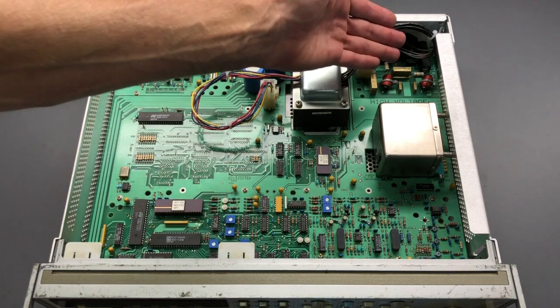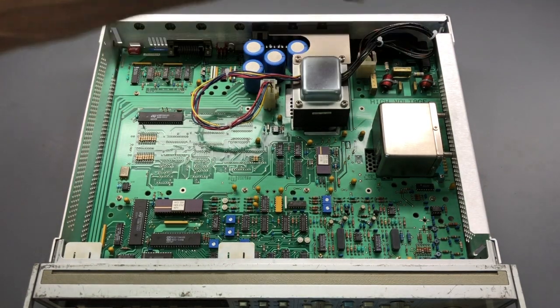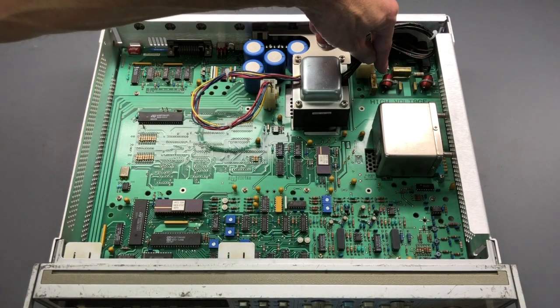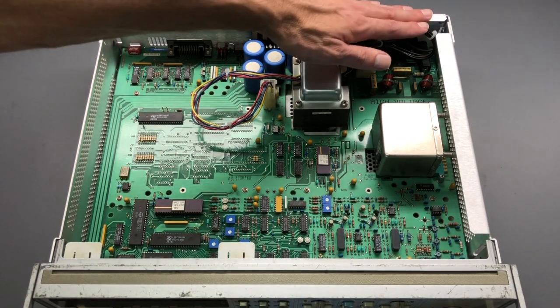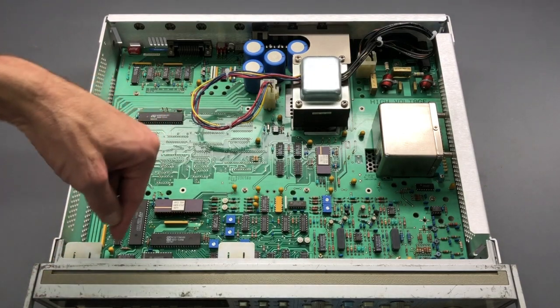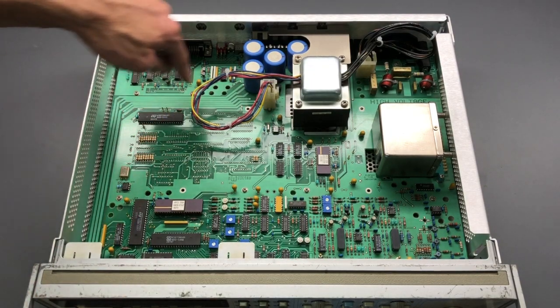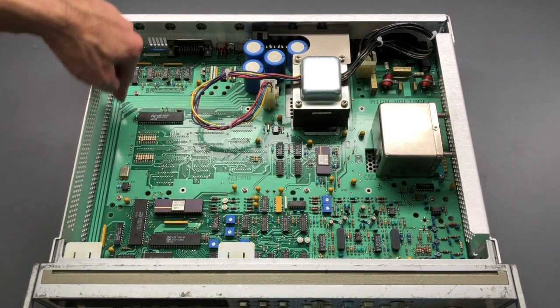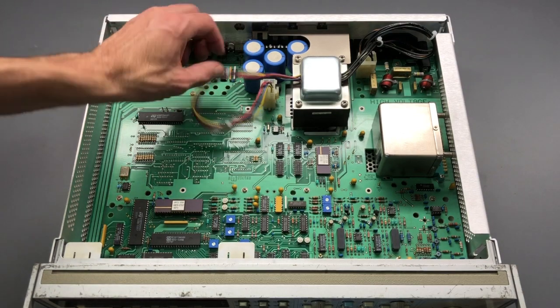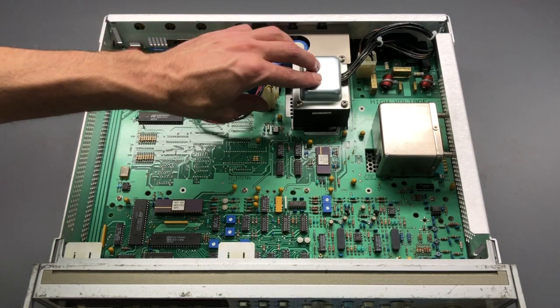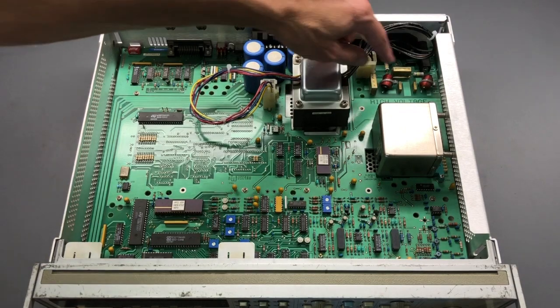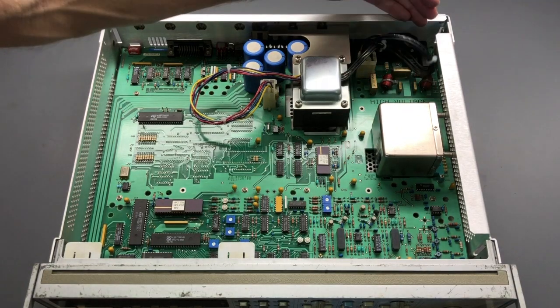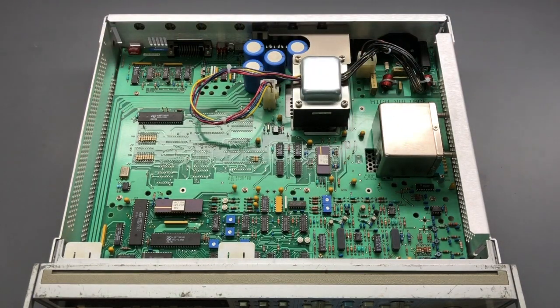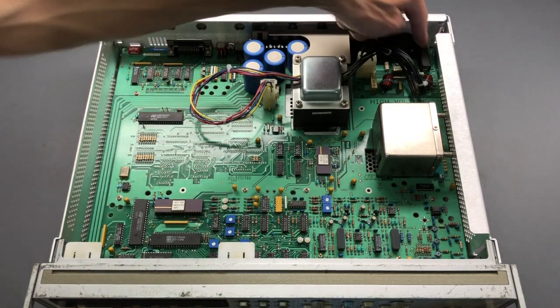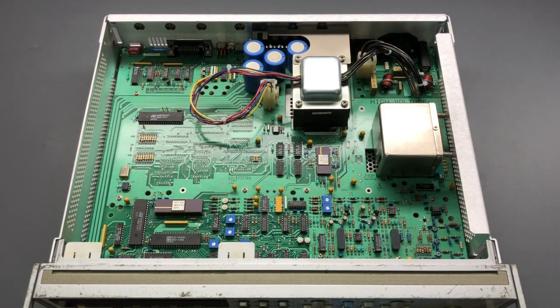And what makes things worse in here is these are on all the time. These are across the AC line, which is not switched. The main power switch is over in this corner. You can see the traces on the board right here that go to the switch right here, and they're really switching the secondary on the transformer. This is not switched. So if one of these goes, it is right on the AC line, and it's not even going to be switched. You certainly would hope that the fuse fails or something protects things, but if one of those goes, it is right on the AC line.